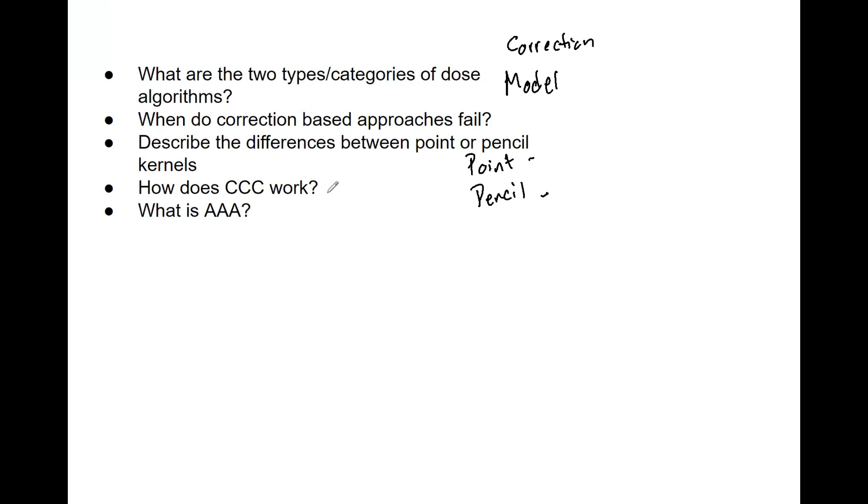Now collapsed cone convolution, CCC, ignores multiple scattering events—that speeds up the calculation. Remember, this isn't as accurate as Monte Carlo, but Monte Carlo takes a very long time and probably in most cases isn't clinically viable because it takes so long.